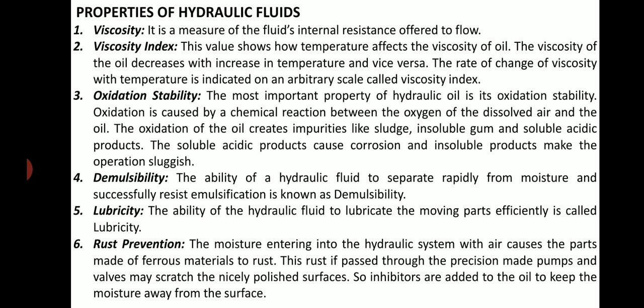Rust prevention: The moisture entering into the hydraulic system with air causes the parts made of ferrous materials to rust. This rust, if passed through the precision-made pumps and valves, may scratch the nicely polished surfaces. So inhibitors are added to the oil to keep the moisture away from the surface.